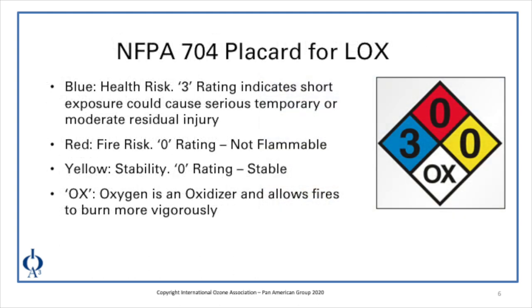At liquid oxygen facilities, you'll often see an NFPA 704 placard related to the hazards of liquid oxygen. It covers health risk, fire risk, stability, and characteristics of liquid oxygen. The blue part represents health risk — oxygen gets a 3 rating, indicating short exposure could cause serious temporary or moderate residual injury. The red part indicates fire risk, and oxygen has a 0 rating as it is not flammable. The yellow part relates to stability, also 0 since oxygen is very stable. The OX on the bottom indicates oxygen is an oxidizer, which may lead to fires burning more vigorously.